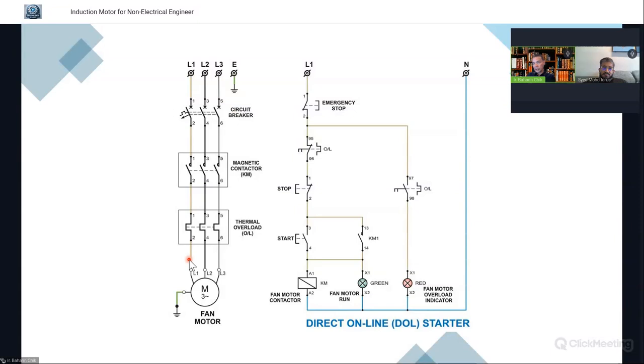But if there is a fault on the cable itself going to the motor, the current will be higher. Remember just now there are differences: one is the heat, the other one is the current. So when the current is higher, this one will not trip, but the circuit breaker will trip, because the circuit breaker is designed for the short circuit rather than overload. So there is coordination between the thermal overload and the MCCB. They have to be separate. One cannot do the job of the other.